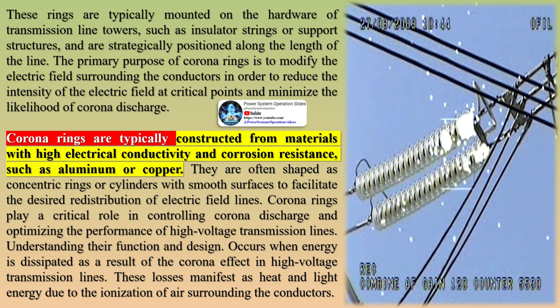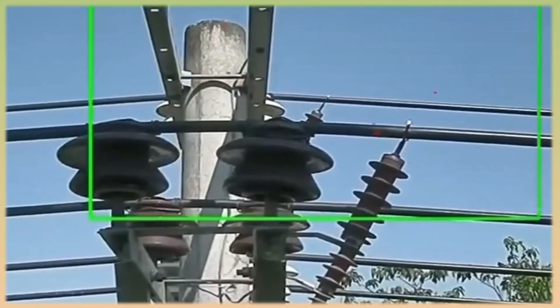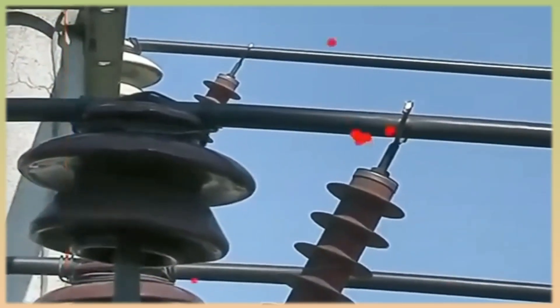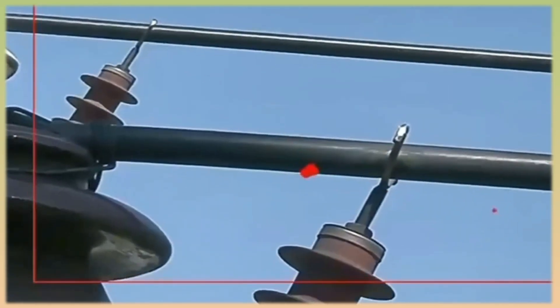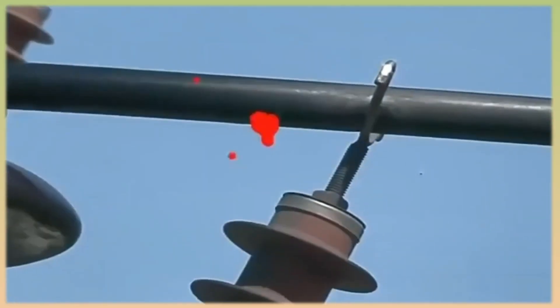These rings are typically mounted on the hardware of transmission line towers, such as insulator strings or support structures, and are strategically positioned along the length of the line. The primary purpose of corona rings is to modify the electric field surrounding the conductors in order to reduce the intensity of the electric field at critical points and minimize the likelihood of corona discharge. Corona rings are typically constructed from materials with high electrical conductivity and corrosion resistance, such as aluminum or copper, and are often shaped as concentric rings or cylinders with smooth surfaces.